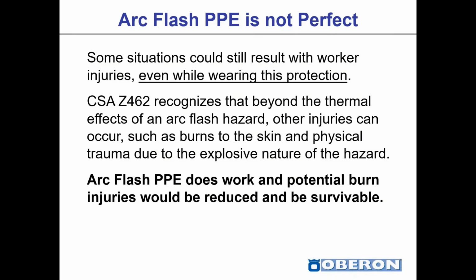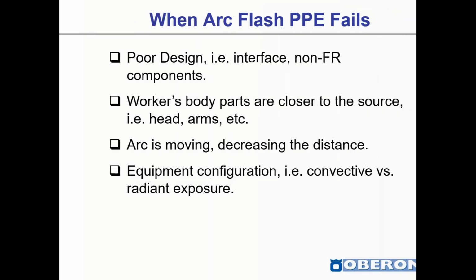Arc flash PPE is not perfect, so some situations could result with a worker being injured even while wearing their protection. The CSA Z462 standard recognizes that beyond the thermal effects of an arc flash hazard, other injuries can occur. Arc flash PPE does work, and potential burn injuries would be reduced and be survivable. Just important to note that there are elements to an arc flash that are unpredictable. So it's important that you wear your PPE, but it's not rock solid. You're not wearing a cinder brick wall for protection from the arc flash.